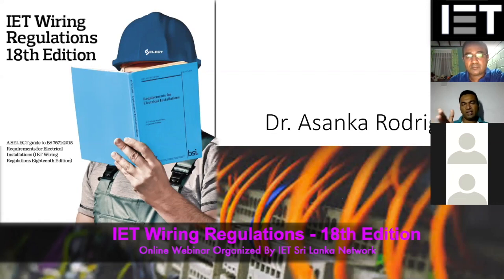But as I said, in the zone 2 area you can use a normal luminaire and other equipment if you are going with SELV equipment, then you can install it in that area. But in the outside zone, you can use any equipment as in a normal installation. Even within the bathroom, if it is outside the zones, then it's fine. Otherwise, you have to use that particular special equipment like SELV equipment.